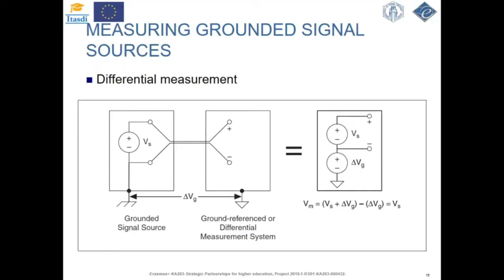When we measure a grounded signal source with a differential measurement setup, we solve the problem stated in the previous slide. Namely, as we can see in this case, the measured voltage cancels the contribution of the potential difference between the signal source ground and the measurement system ground, which is actually delta Vg. And therefore, in this case, no ground loops are introduced.